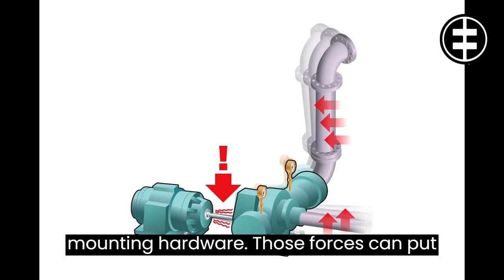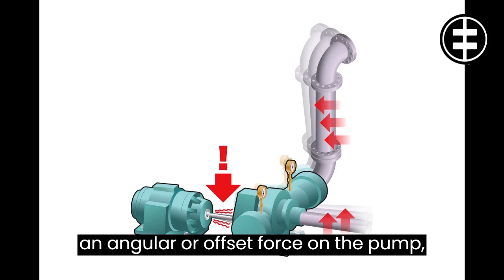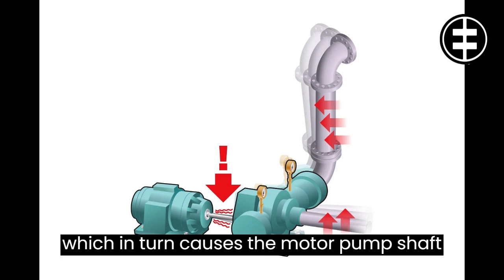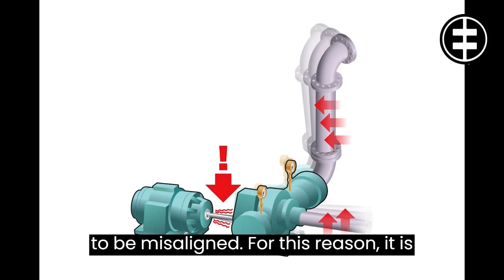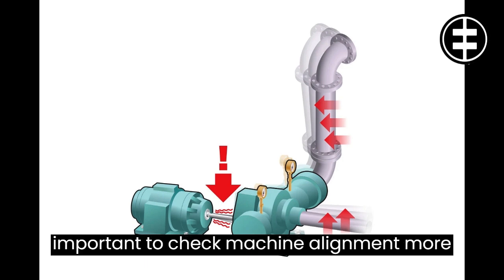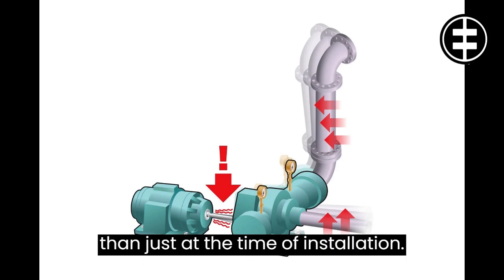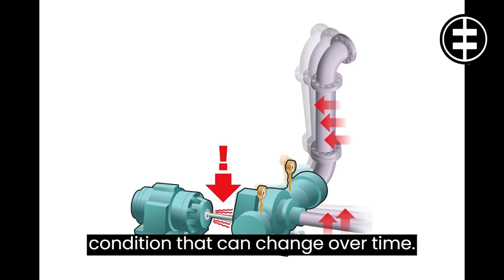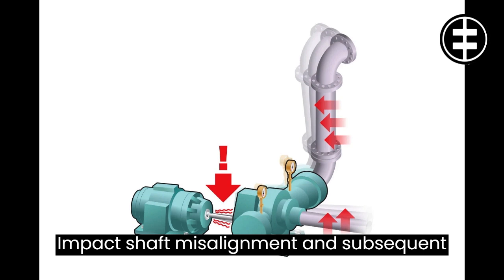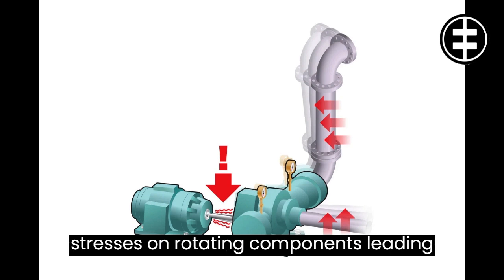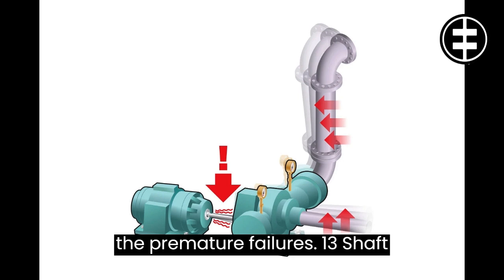Those forces can put an angular or offset force on the pump, which in turn causes the motor pump shaft to be misaligned. For this reason, it is important to check machine alignment more than just at the time of installation. Precision alignment is a temporary condition that can change over time. Impact: shaft misalignment and subsequent stresses on rotating components, leading to premature failures.